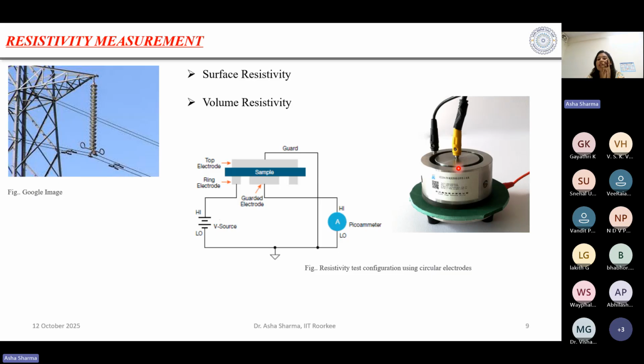We arrange them in such a way that we give a high voltage to the top electrode, and the other electrodes are grounded, and we connect a picoammeter. Since we are talking about an insulator, the current flowing across this will be in the picoampere range only. So using this three electrode arrangement, we try to measure the resistivity of the insulating material.